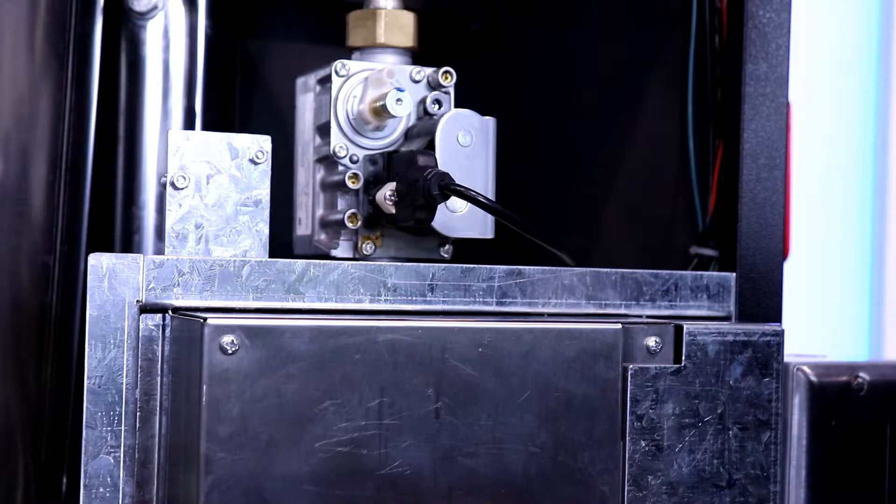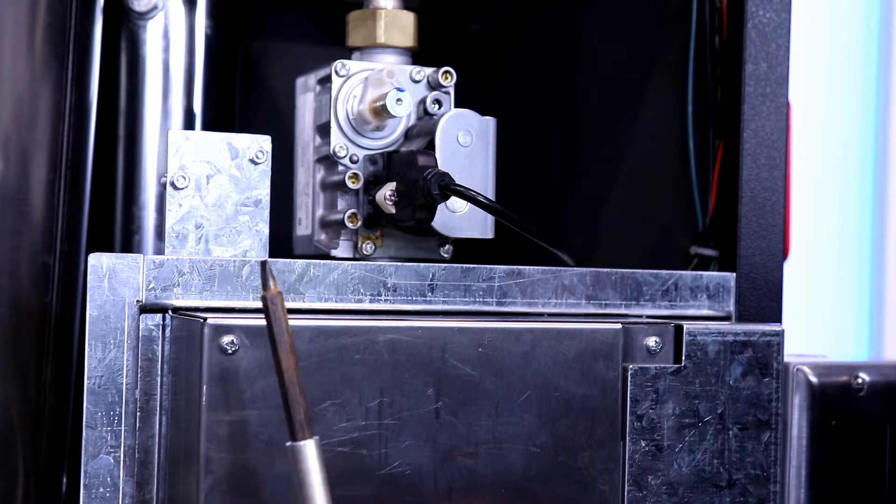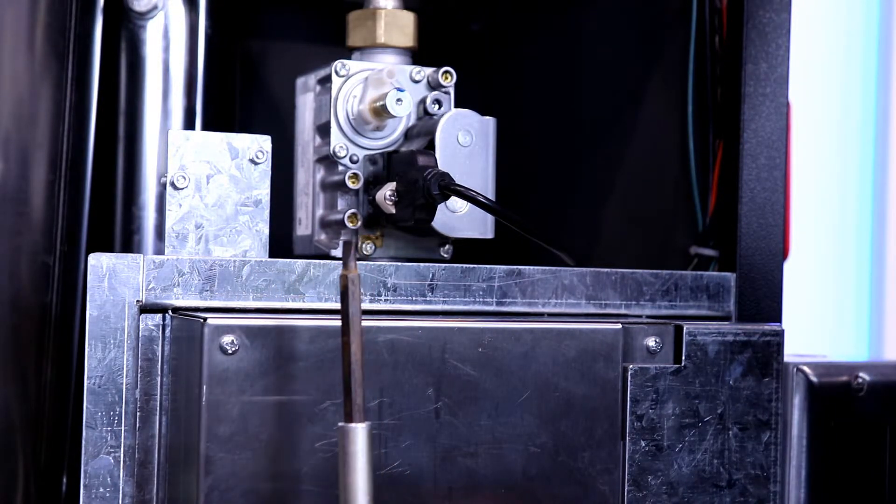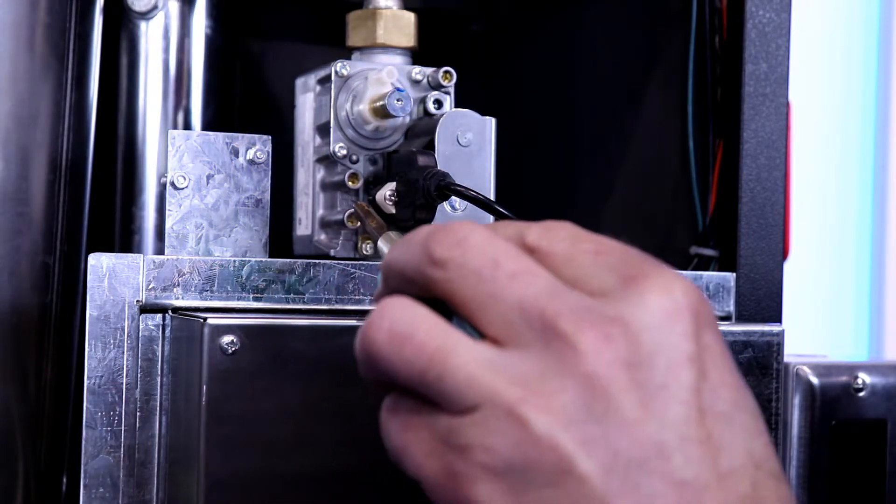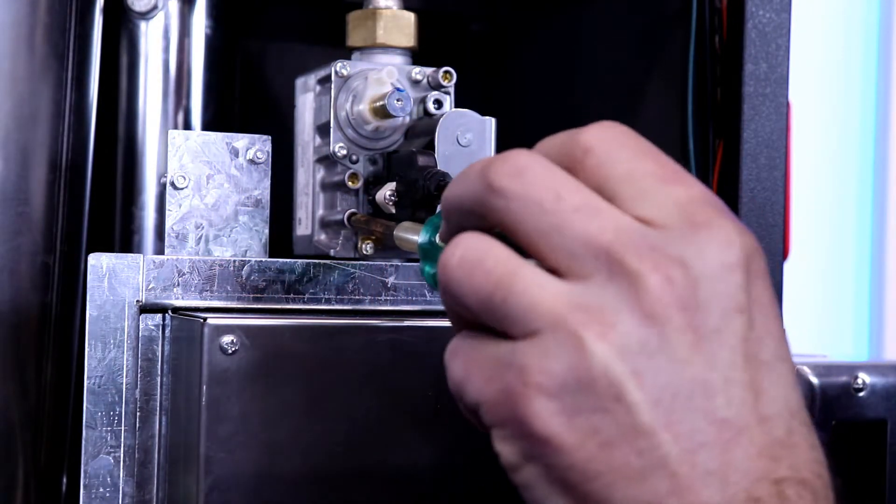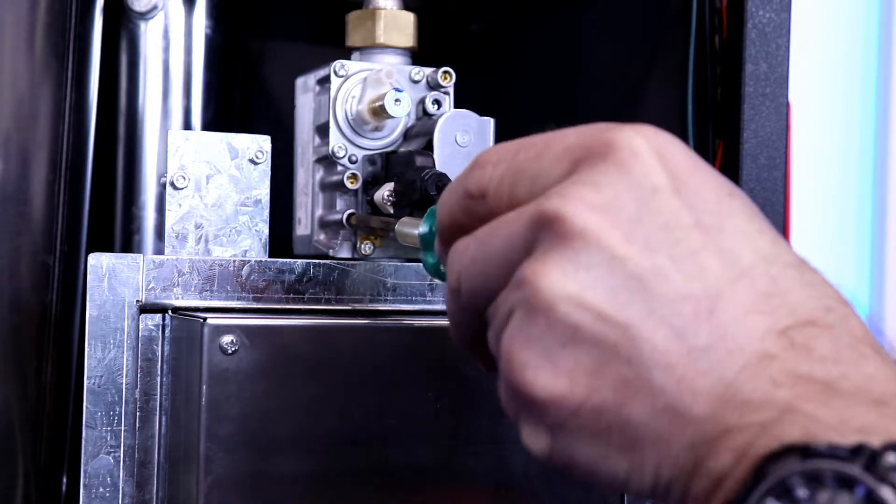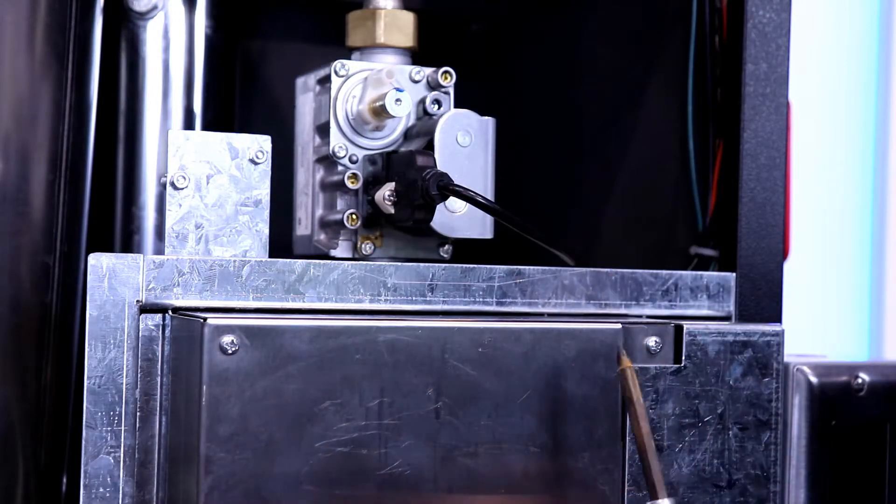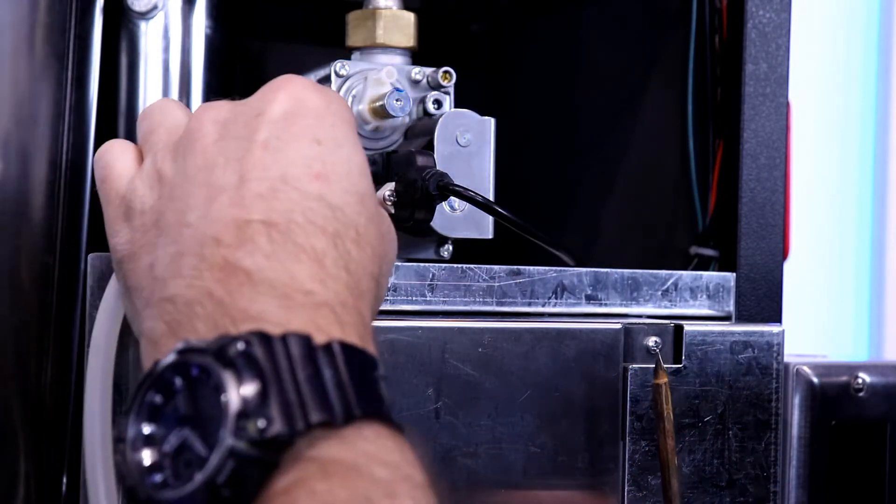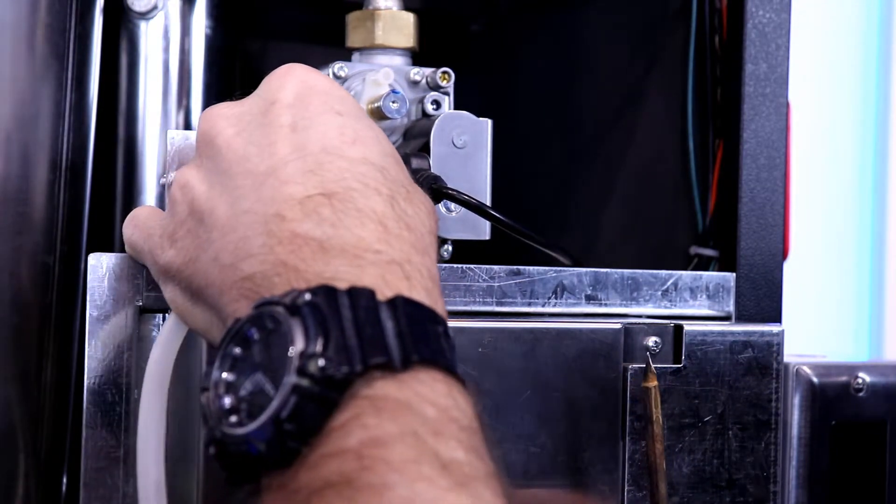we are going to use either a flat blade screwdriver or a T15 Torx to open the set screw inside the gas inlet test port and then attach our manometer pipe to that test port.